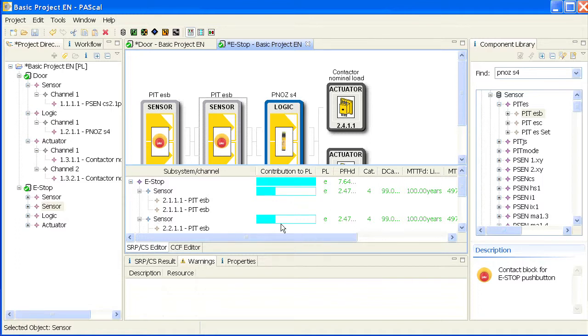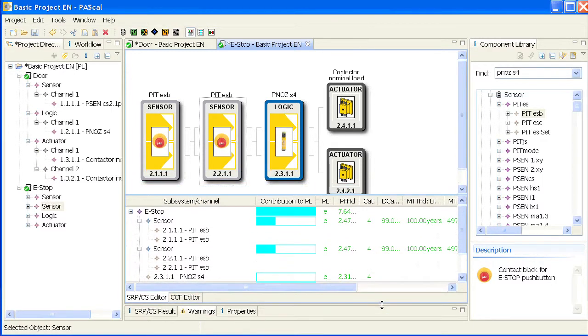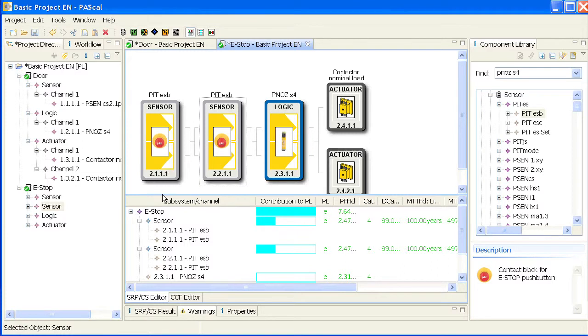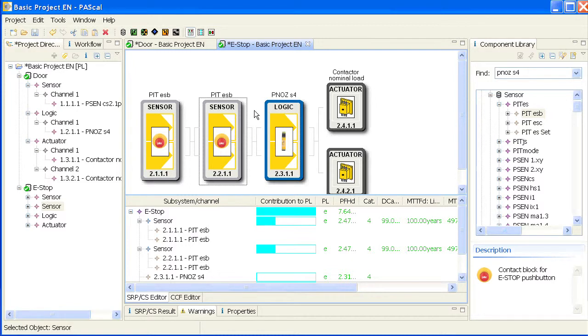What you see right here is that the e-stop comes up at the end with two showing PLs, one for the first and one for the second e-stop. If you add more than two or three of these e-stops you will find yourself dropping down to performance level D simply because each is calculated as an individual subsystem. What can we do?